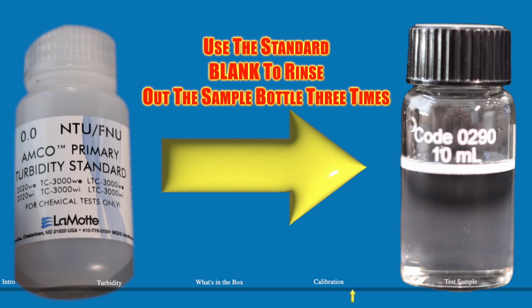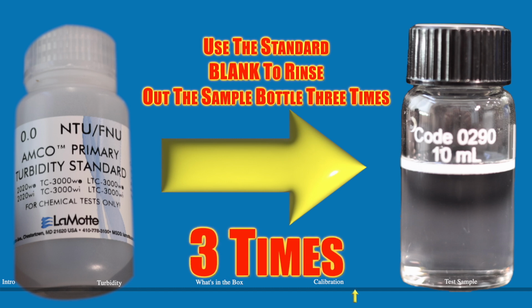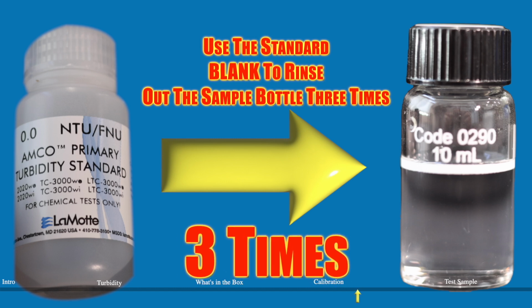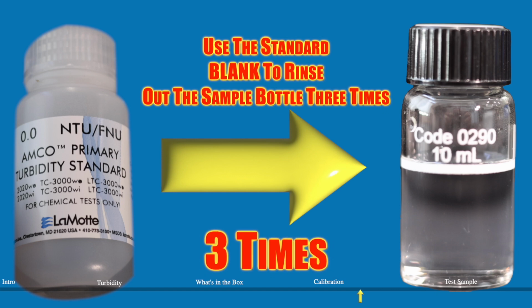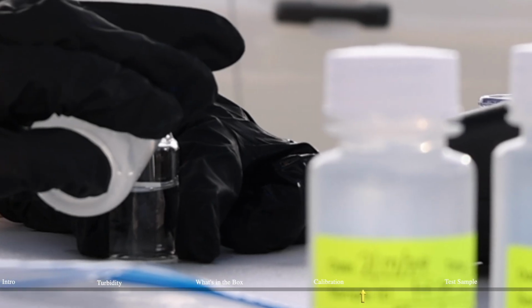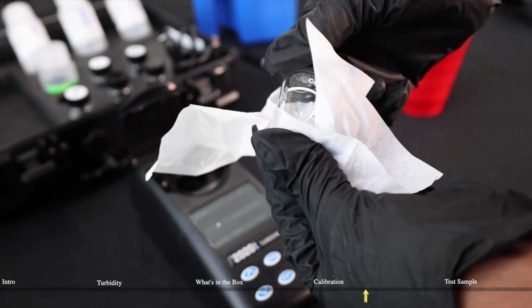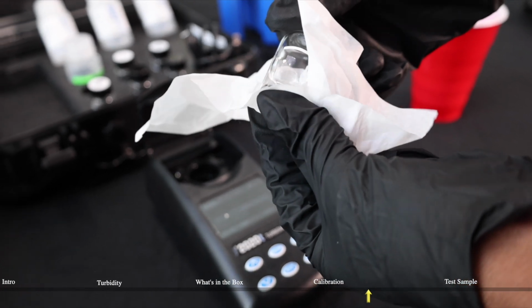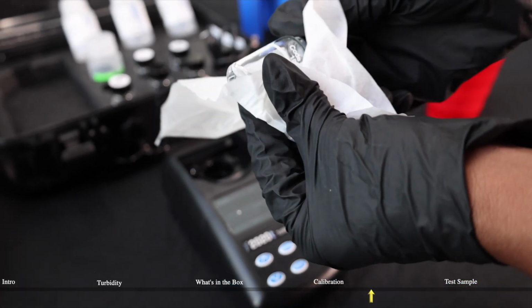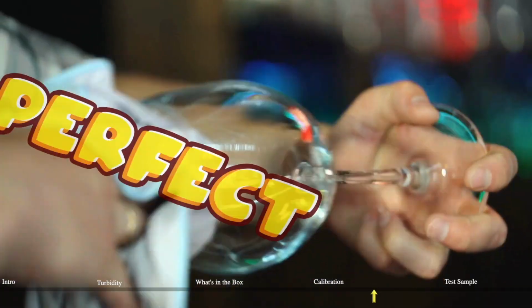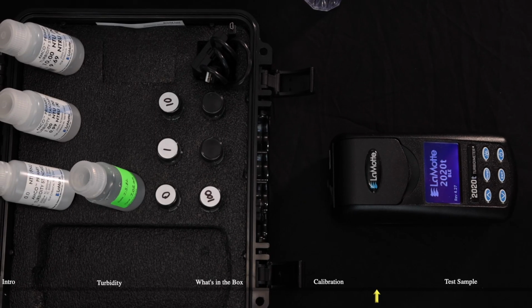Using our gloves, the first thing we want to do is grab a sample tube and the standard blank. Use the standard blank to rinse out the sample tube 3 times. On the 4th time, be sure to fill it up to the line and screw the lid back on. And holding the lid with one hand, use a lint-free cloth to wipe the glass as clean as possible. Perfect! Now we can turn the meter on.